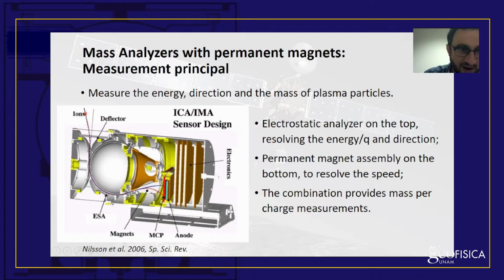So here we have permanent magnets that bend the particle trajectories according to the Lorentz force. And if you put the math down, you will see that the lighter particles will be deflected further away from the symmetry axis of the instrument, which is somewhere here. And heavier ions will land closer to the symmetry axis. Now, the position-sensitive detector can give you the radial distance of the particles, and this can be translated to mass per charge equivalently. So you have a mass spectrometer by using permanent magnets instead of time of flight.